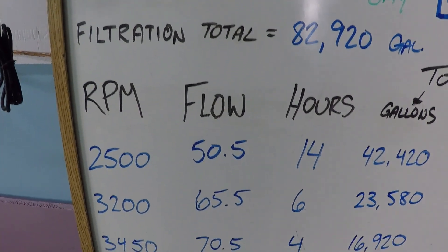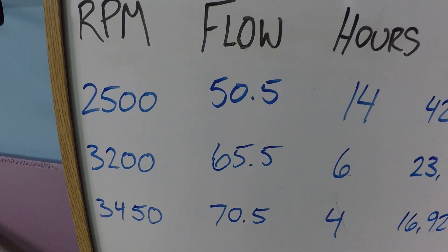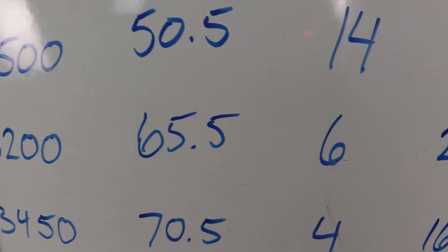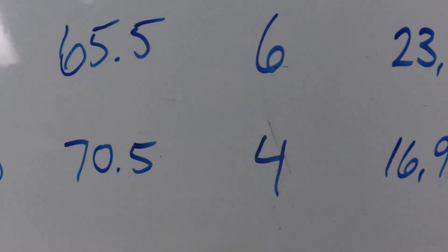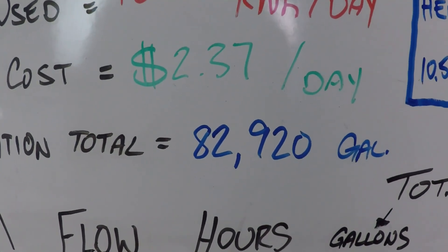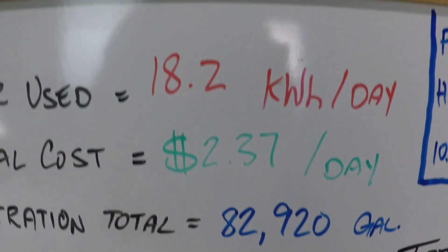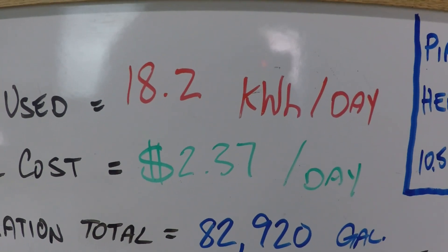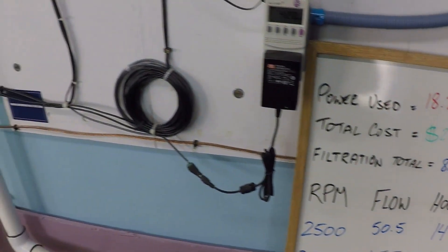Instead of just running a single speed pump around the clock, we've got a 24-hour variable speed schedule using 2500 RPM for 14 hours, 3200 RPM for six hours, and 3450 — which is max speed — for four hours. After 24 hours we're going to have filtered just under 83,000 gallons of water, used 18.2 kilowatt hours of power, and that will cost about two dollars and 37 cents.